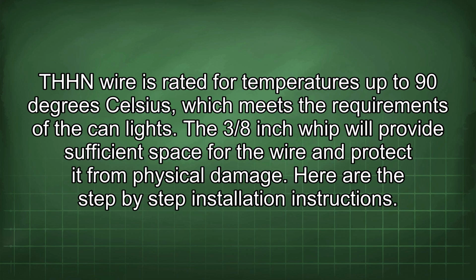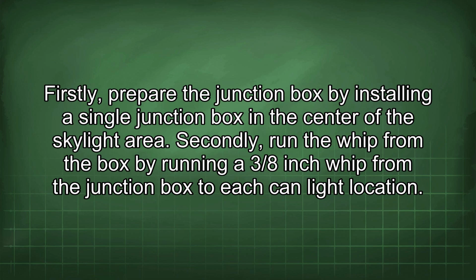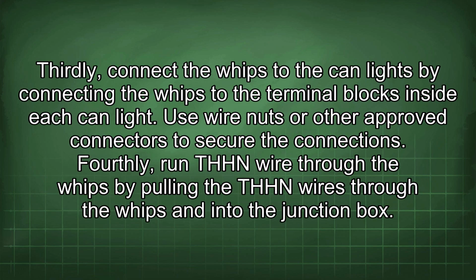Here are the step-by-step installation instructions. Firstly, prepare the junction box by installing a single junction box in the center of the skylight area. Secondly, run the whip from the box by running a 3/8" whip from the junction box to each CAN light location. Thirdly, connect the whips to the CAN lights by connecting the whips to the terminal blocks inside each CAN light. Use wire nuts or other approved connectors to secure the connections.